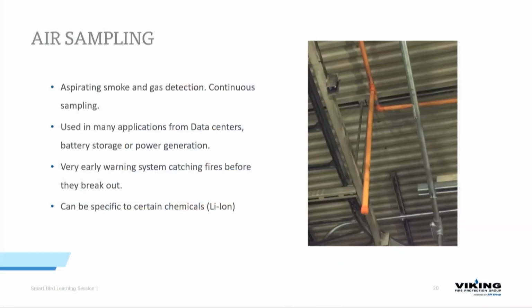All right, so here's one of the newer technologies that's really coming of age right now, and it's air sampling. Think of it like this: you have a smoke detector in a room. That smoke detector just sits there and passively waits for a fire to bring smoke to it. Aspirating smoke and gas detection continuously samples the air. It's continually pulling air with a vacuum so that it can tell you before you have a fire if there are chemicals present in your air that indicate you might be in a situation that could become a fire. When we go back to that fire triangle and talk about the chemical reaction, these systems are sniffing for that chemical reaction. That's what they're there to do.